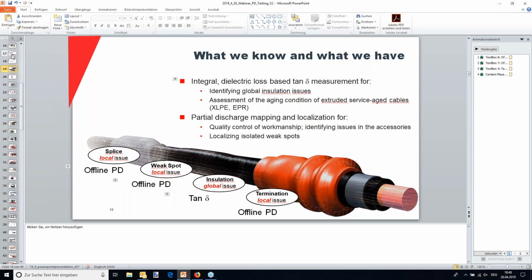But if you put in a rubber mat or any kind of barriers, what happens from a high voltage point of view is that the so-called dielectric flow hits you, because the electric field lines behave differently when there is a material in the presence of the electric field that has a permittivity dissimilar to air.